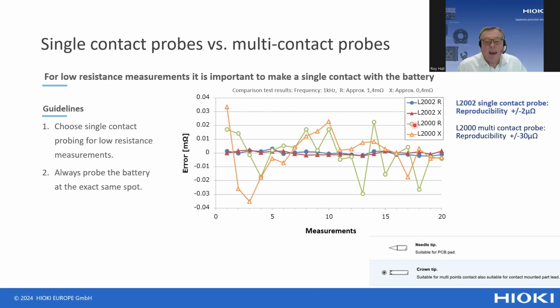But if you look at the connection with the multi-connection probe, you can see that it's all over the place. There is a reproducibility error of almost 30 microohm. And when you consider that your battery has an internal resistance of less than 1 milliohm, this is something that you have to consider. So, in general, the conclusion is that you should use a single contact probe to get good repeatable measurements.